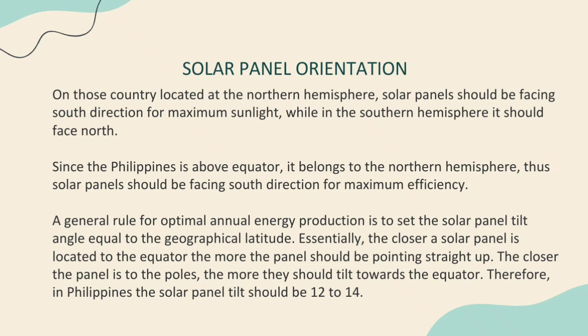Since the Philippines is above the equator, it belongs to the northern hemisphere, thus solar panels should be facing south direction for the maximum efficiency. So pag sa Philippines po tayo, ang solar po ay dapat ay nasa south. Nakatapat po dapat siya sa south. A general rule for optimal annual energy production is to set the solar panel tilt angle equal to the geographical latitude. Essentially, the closer a solar panel is located to the equator, the more the panel should be pointing straight up. The closer the panel is to the poles, the more they should tilt toward the equator. Therefore, in the Philippines, the solar panel tilt should be 12 to 14 degrees. So dapat po naka-tilt po yung solar nyo. Kapag install nyo po siya, dapat naka-tilt po siya ng 12 to 14 degrees.